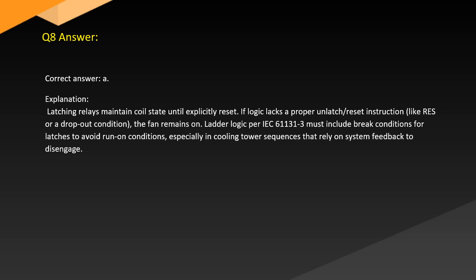Answer. Correct answer: A. Explanation. Latching relays maintain coil state until explicitly reset. If logic lacks a proper unlatch or reset instruction, like a reset or a dropout condition, the fan remains on. Ladder logic per IEC 61131-3 must include break conditions for latches to avoid run-on conditions, especially in cooling tower sequences that rely on system feedback to disengage.